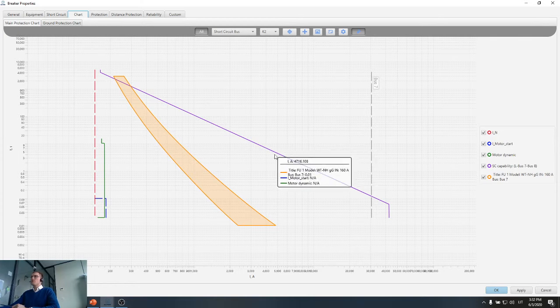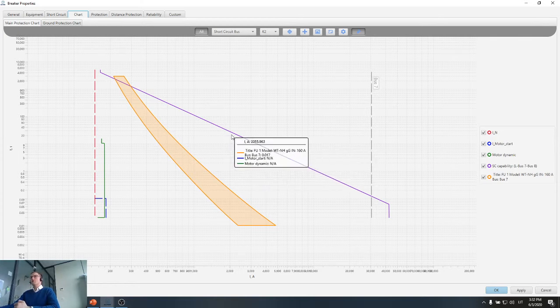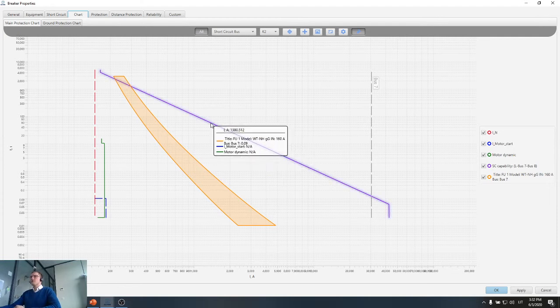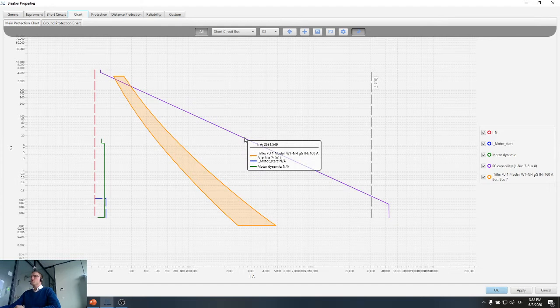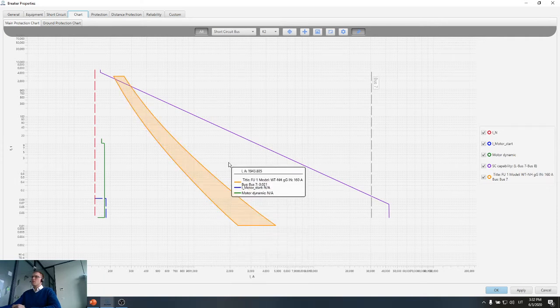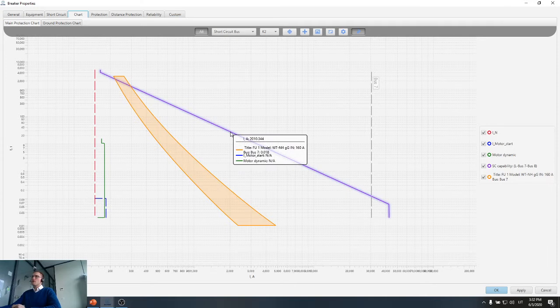On the picture here we also have a short circuit capability curve. This short circuit capability curve, which is provided in purple color, is showing how much time it will take for the cable to overheat during the short circuit. In this case it's cable, but in some other cases it can be a transformer or other type of equipment. So for example, if our short circuit current is 2000 amps, as we can see here in the lower axis, let's move up to the capability curve, and we see that our overheating time is around 20 seconds, a little bit more than 20, something from 20 to 30 seconds exactly.